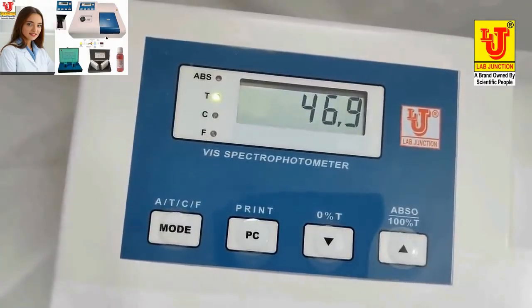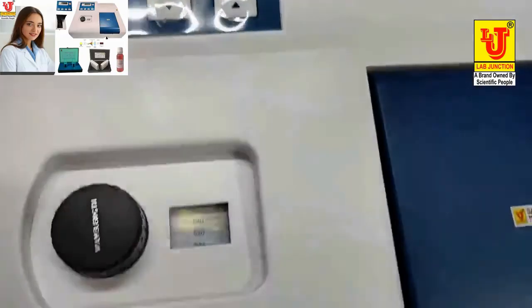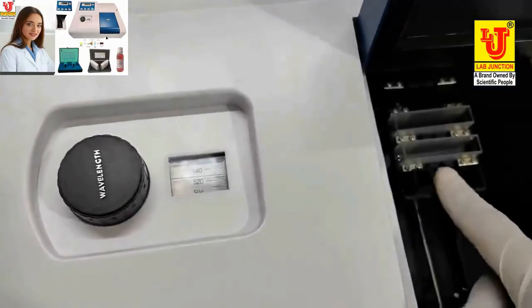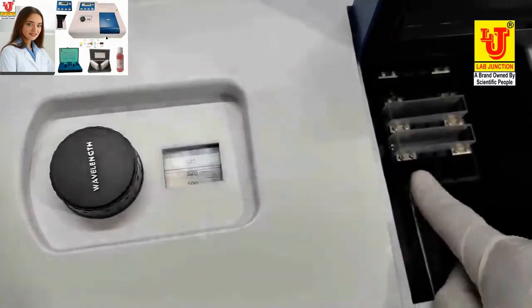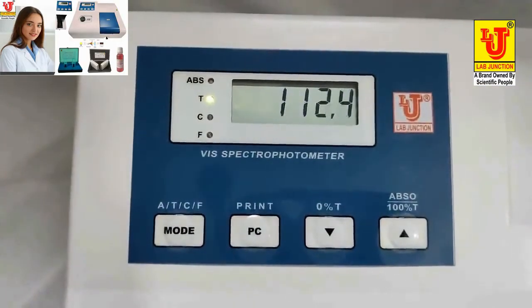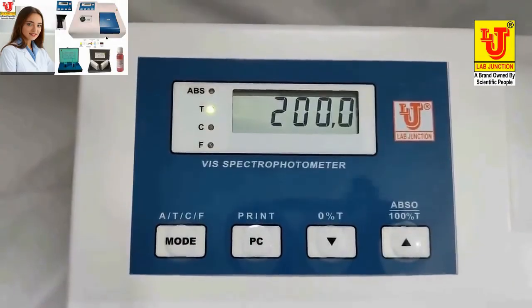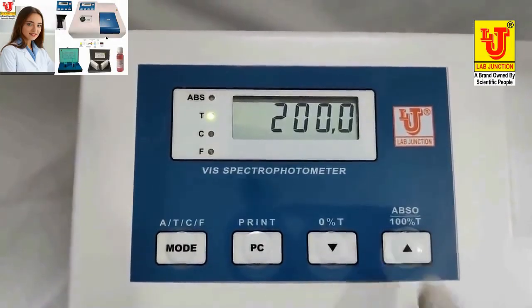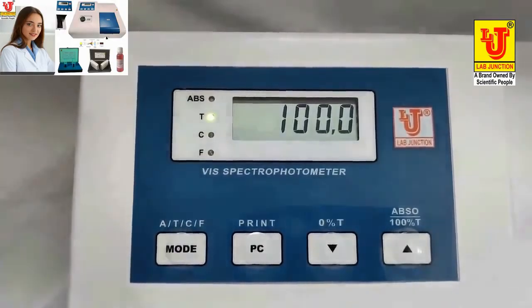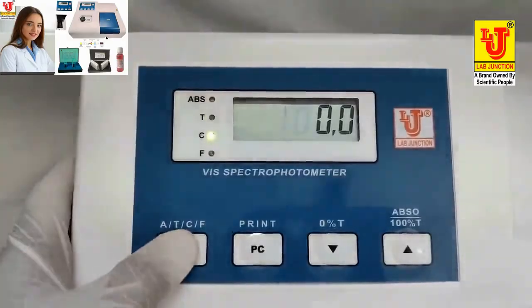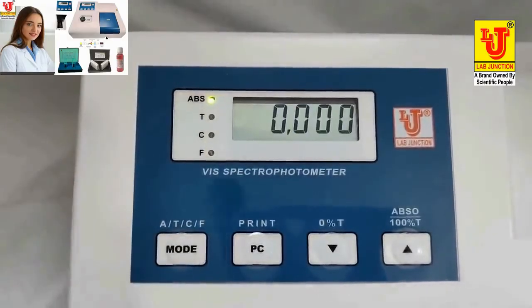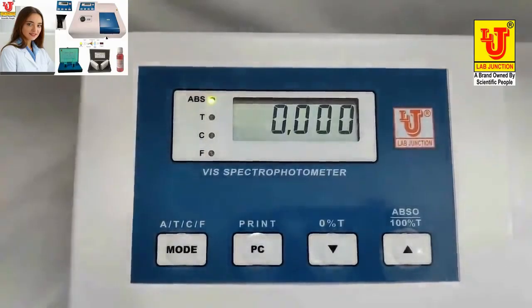This is not working. Why? I am not placing this properly. See, this is on the dummy side. So when I go to transmission this way, now pressing 100. Now 100% transmission is there. Now I am going to absorbance mode. Absorbance is 0. If transmission is 100, absorbance is 0.